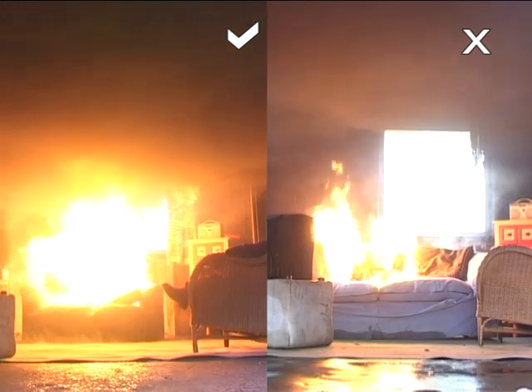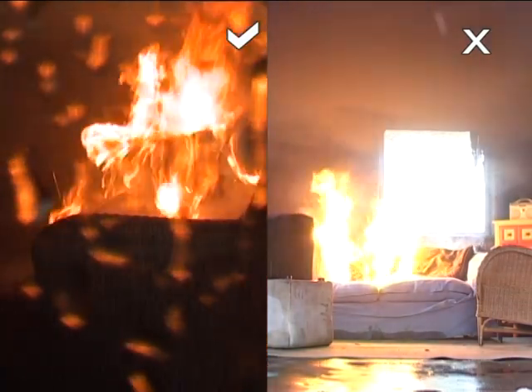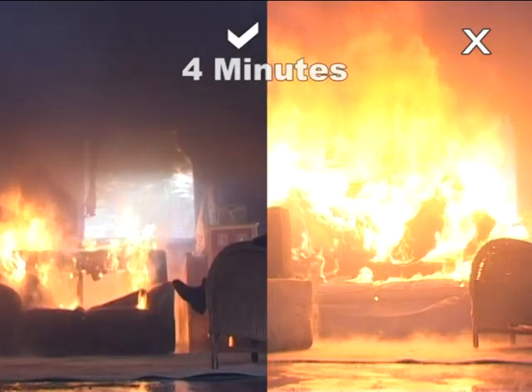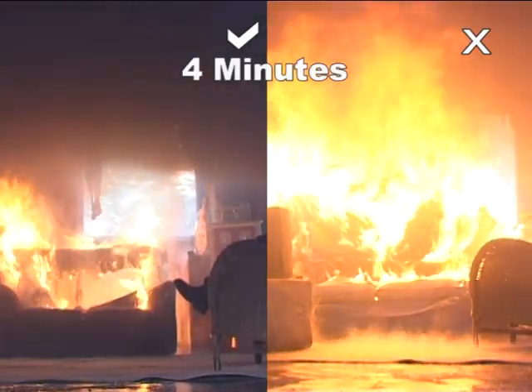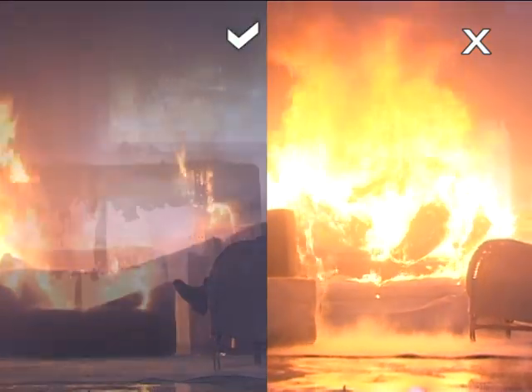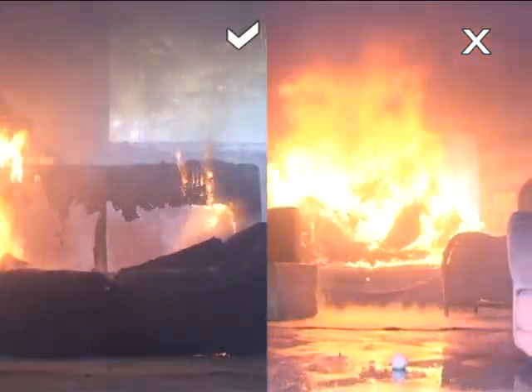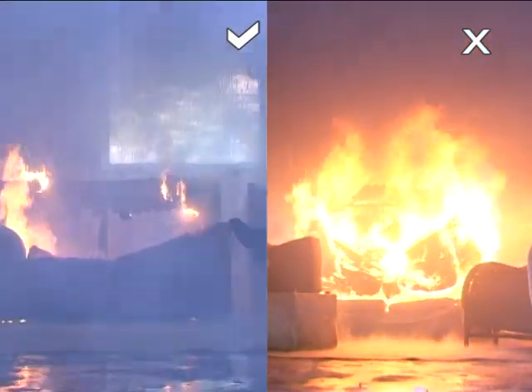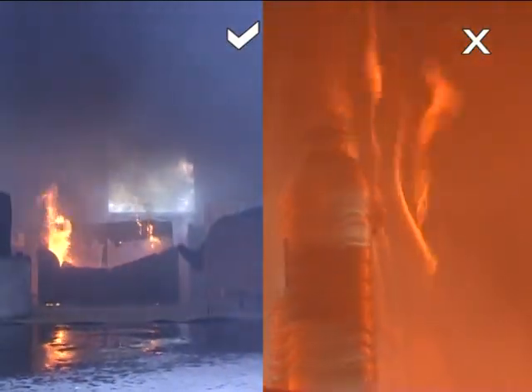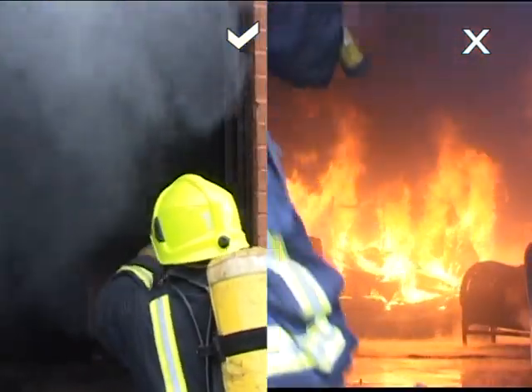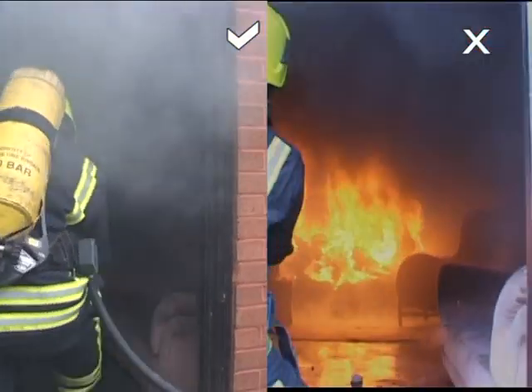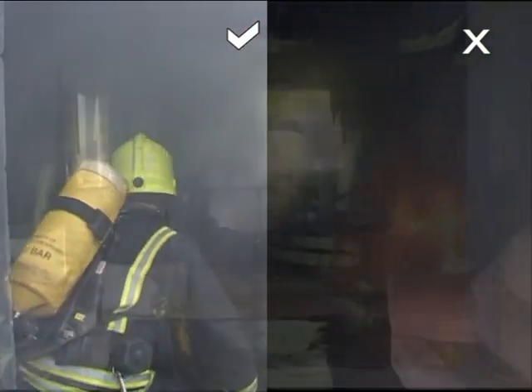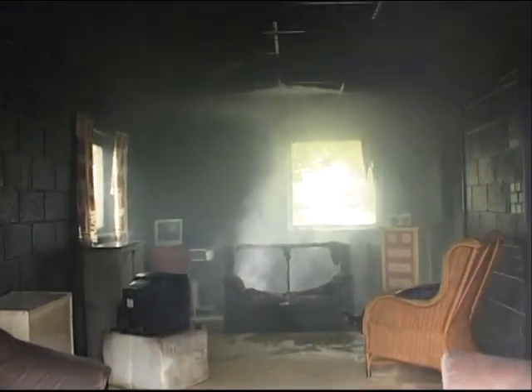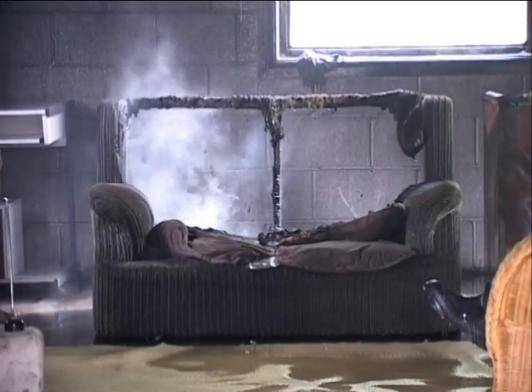After 2.5 minutes, the sprinkler head activates and starts to extinguish the fire. A typical sprinkler head requires around 40 litres of water a minute to operate effectively, but firefighters can use 10 times this amount. In our experience, water damage from sprinklers is so minimal, householders are often able to stay in the property, or at worst, are away for no more than 24 hours. Now the Fire and Rescue Service has arrived to fully extinguish what remains of the fire. This sprinkler intervention hasn't just saved the occupant's life, it has also made the scene far safer for the fire crew.